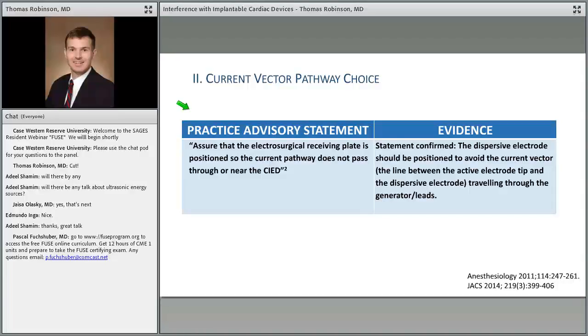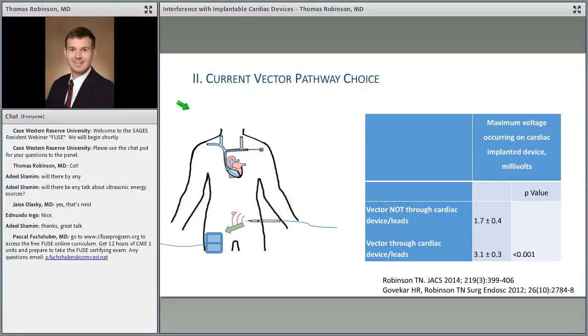The concept is you should position the dispersive electrode, that's the grounding pad, the big sticky pad, so that the straight line between your active electrode tip and the dispersive electrode does not go through the cardiac rhythm management device. Here's a great example. If we're doing an X-lap on somebody, we can change where we put the dispersive electrode, and I don't think anybody would put it up here, say on the left shoulder, right? If you put the dispersive electrode on the left shoulder, the current would go straight this direction and right through your cardiac rhythm management device. That would not be ideal. What you want to do is place it so that the current vector goes down and away from it.